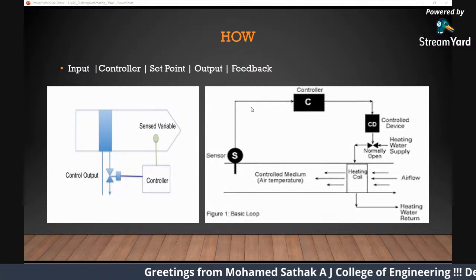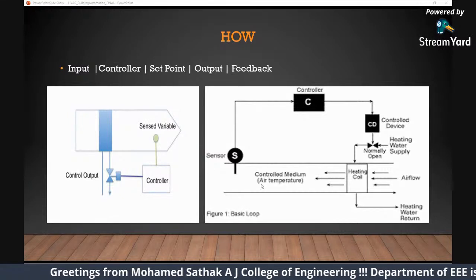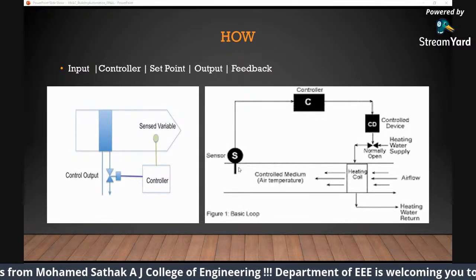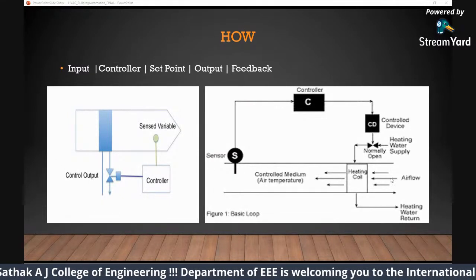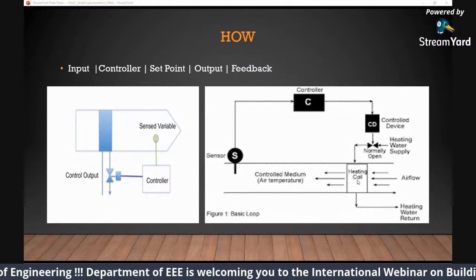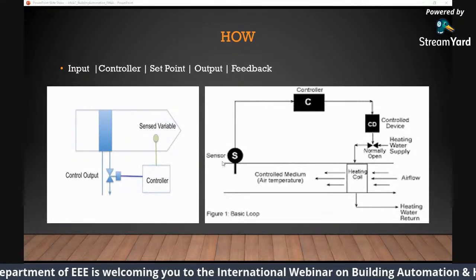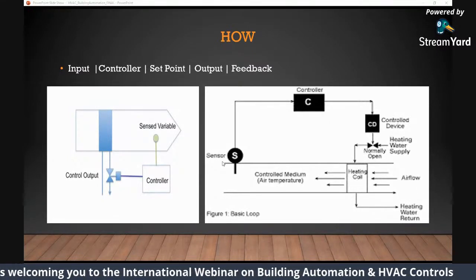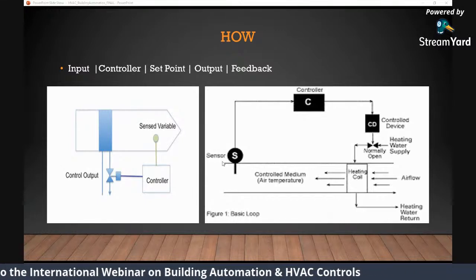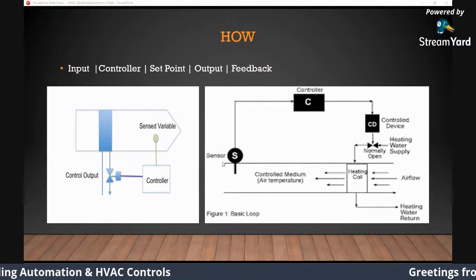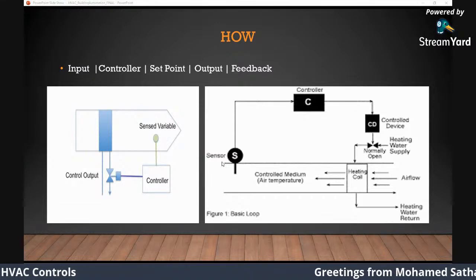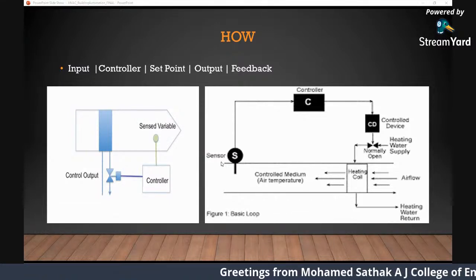Now, if you see the picture on your right, it explains this. Let's take it as an AHU. There's a heating coil. Your air flows from the supply fan to the heating coil. Your sensor is here, which we call the discharge air temperature sensor. It measures the temperature from your AHU consistently. Now, let's say it's too cold outside and you want 30 degrees Celsius from your AHU.